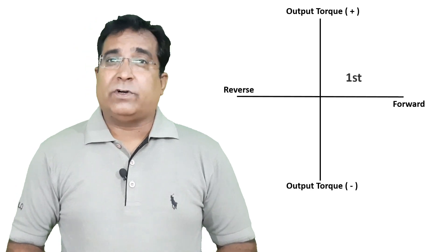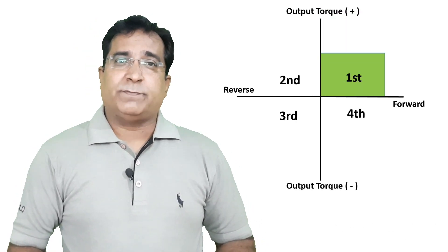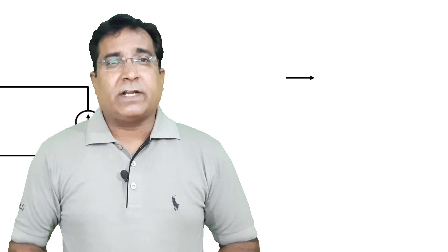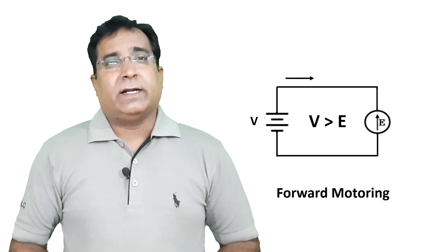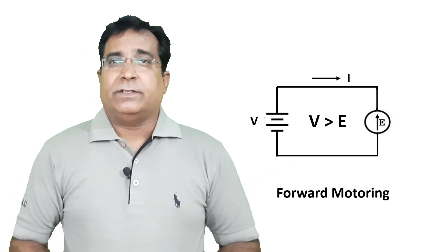So here the forward torque limit in VFD has to be set in terms of percentage of rated torque as per load requirement. The default can be 200%. It can also be understood by electrical circuit. Here the power supply V pumps current I into motor E. Result: you get a forward motion and positive torque.